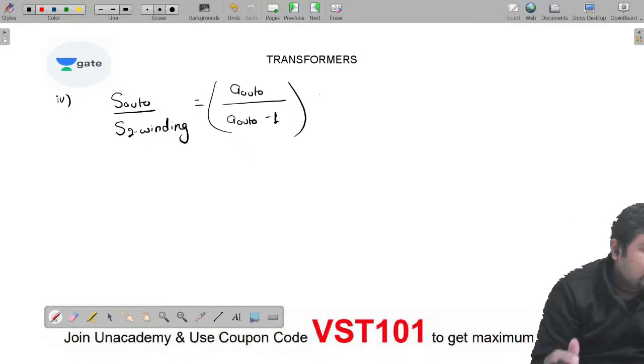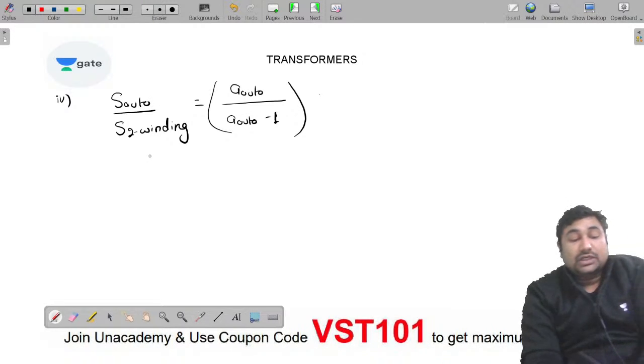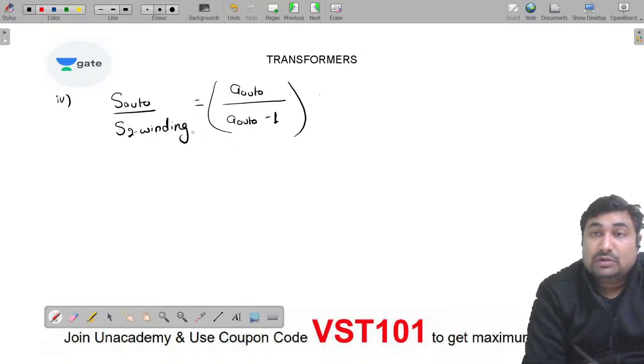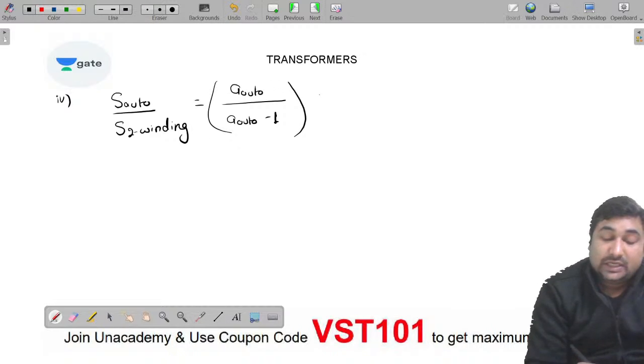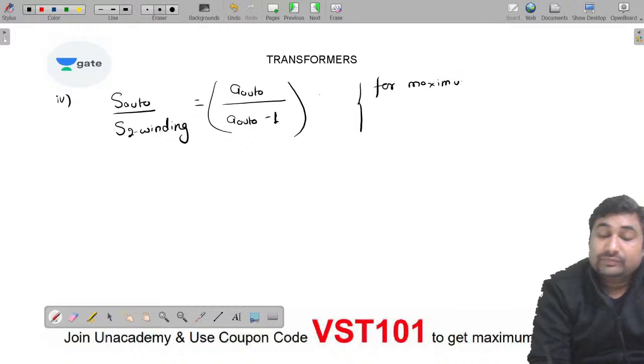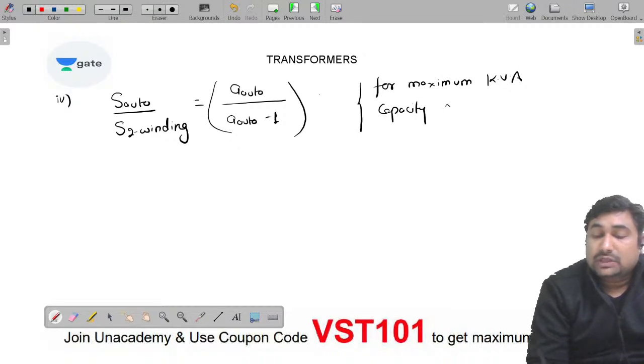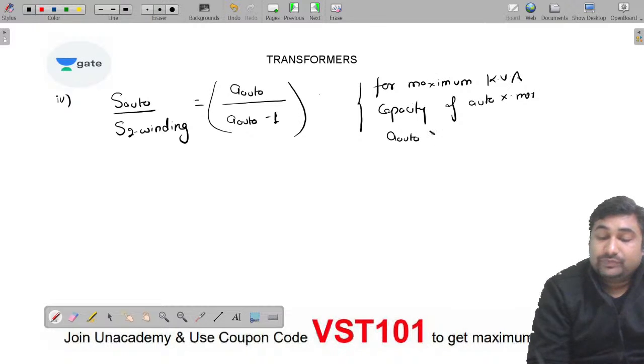How to find the maximum auto transformer rating. Please observe, beta. kVA of auto transformer to kVA of two winding transformer, when the same amount of material is being used, can be represented as A auto upon A auto minus 1. You have to remember one thing here, that for maximum kVA capacity of auto transformer, A auto should be close to 1. Okay, so A auto is close to 1.